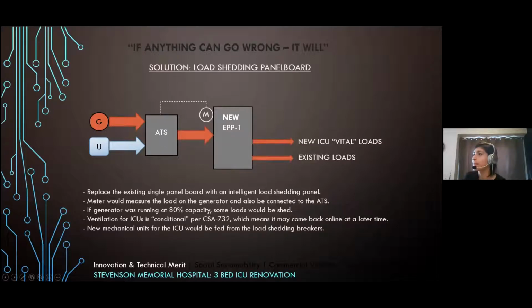And what we discovered, or established, was that the ventilation for an ICU is classified as a conditional load. So we were able to put the ventilation units for our new ICU on those load shedding breakers, effectively creating a conditional branch of power and salvaging some of the load on the generator. This made our project possible. If we hadn't been able to do this, it wouldn't have been possible to feed the new ICU.